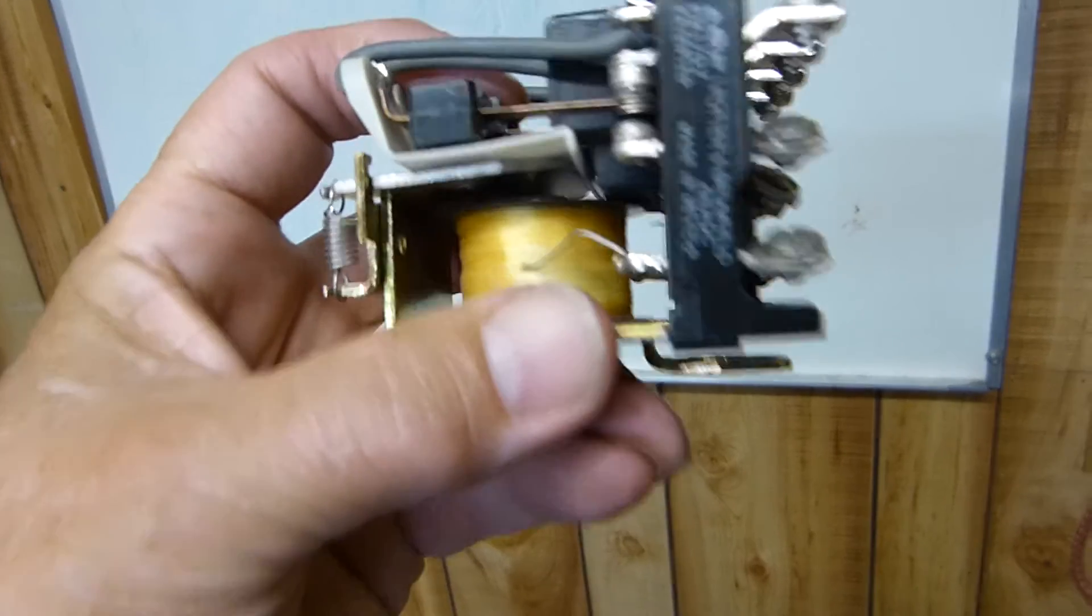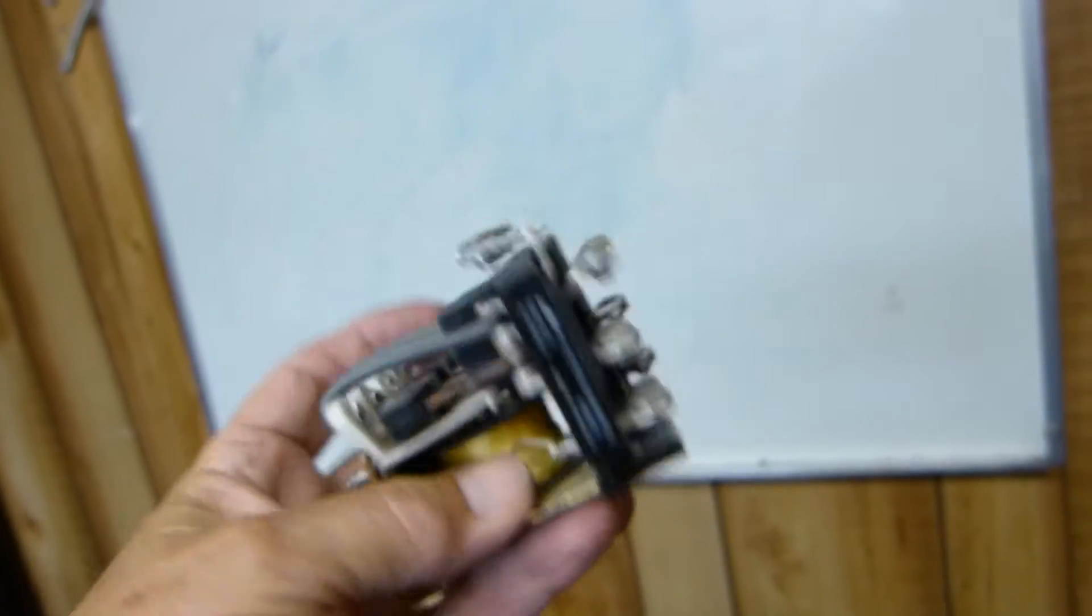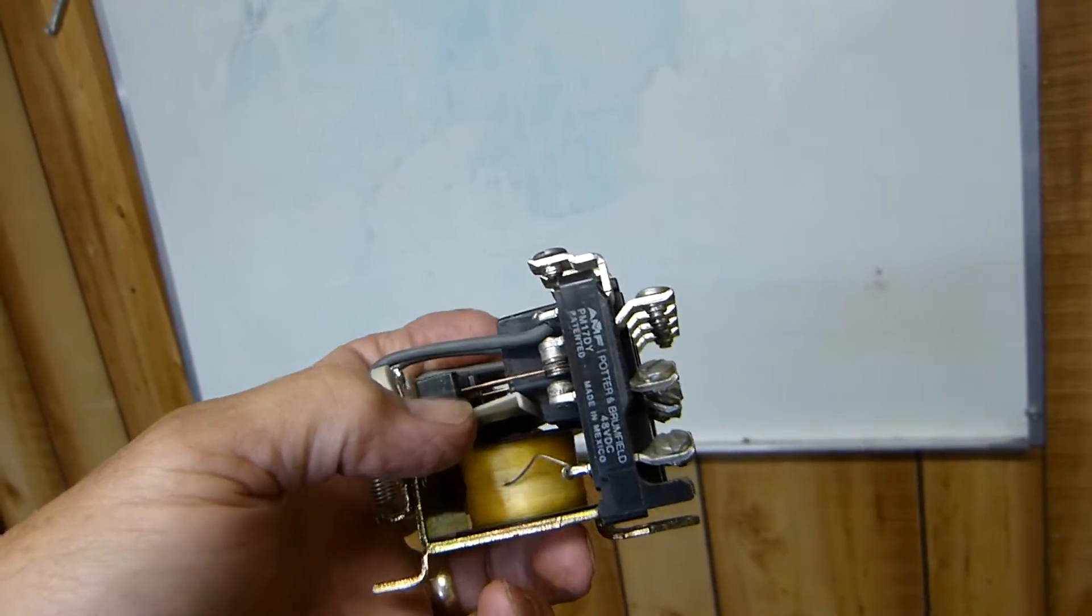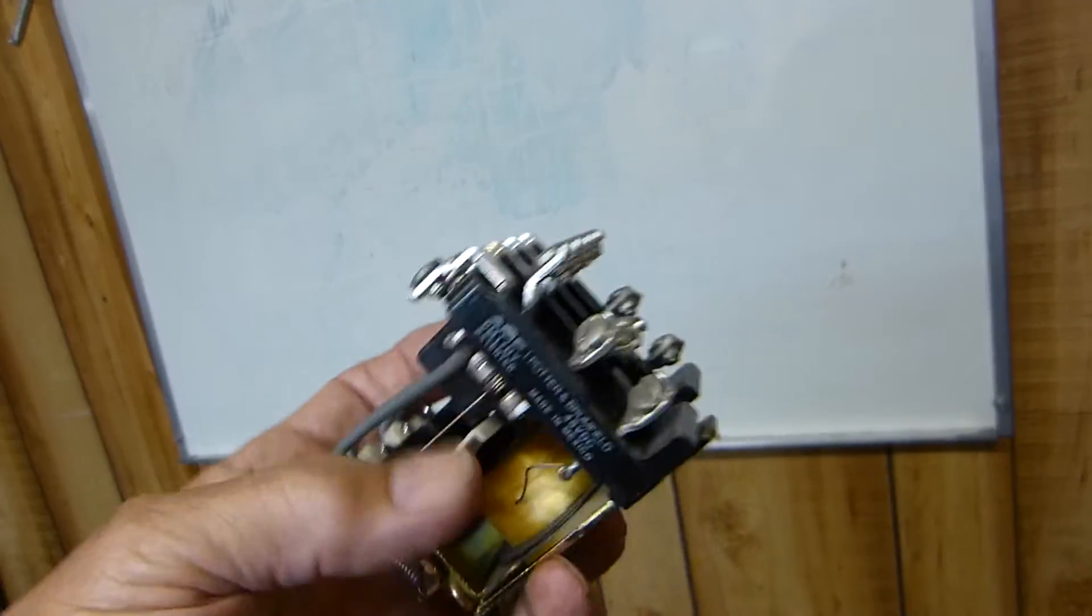When the coil is energized, it changes state right there. This one's got four sets of contacts on it. Each contact is a single pole double throw. It's got four of them, so it's got four poles double throw. Double throw means it's got two positions that it can operate in.